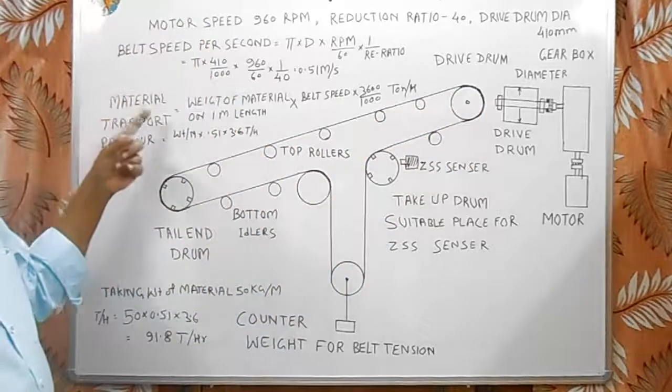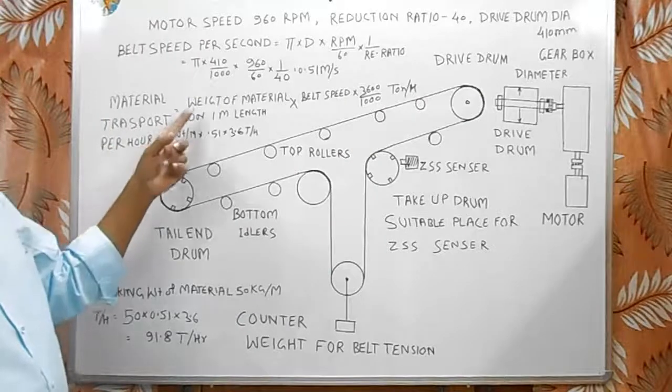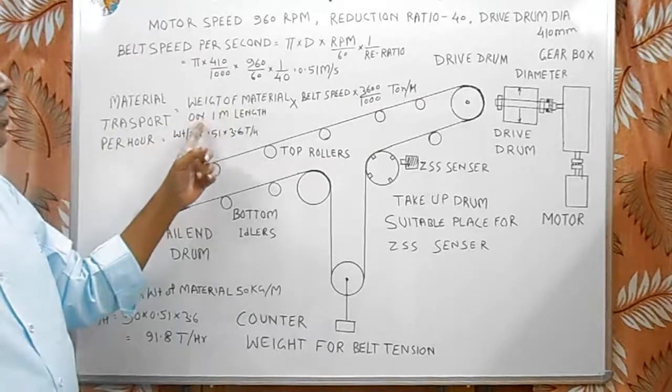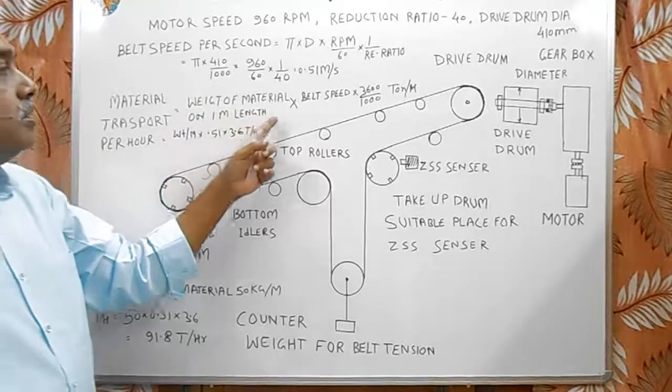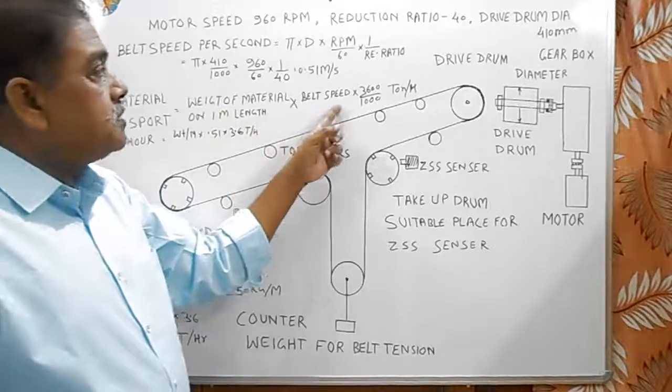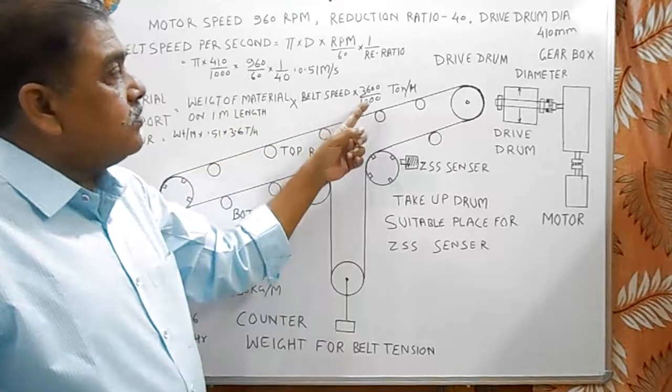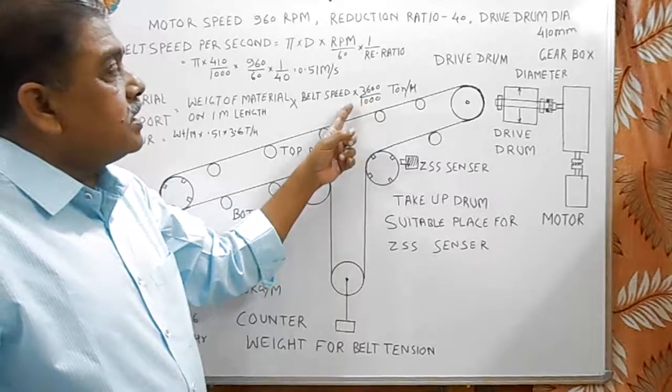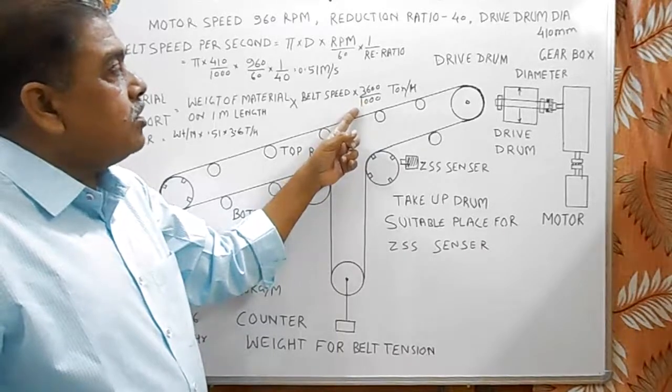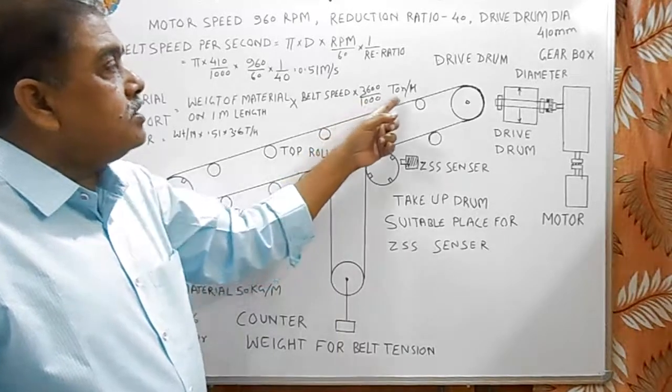Then material transported per hour is equal to weight of material on 1 meter length of the belt multiply by belt speed into 3,600 for 1 hour, means seconds in 1 hour, divided by 1000 to convert it into tons per hour.